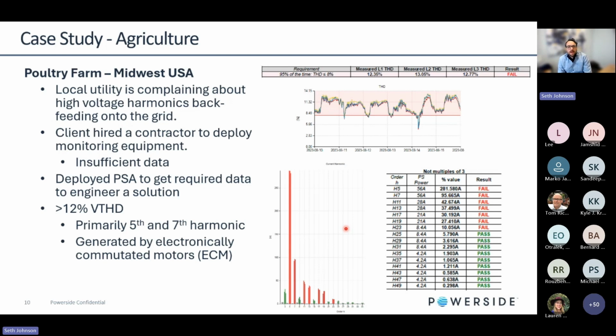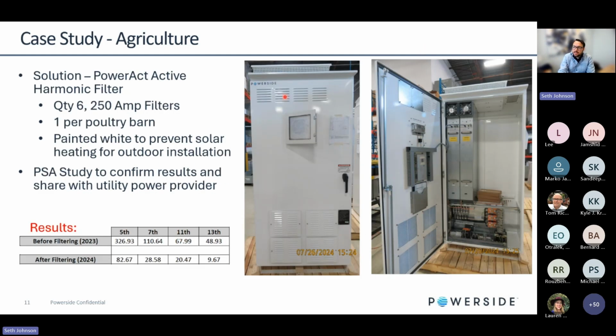And so what we offered was our Power Act product line. And you can see images here of the actual units that we shipped this client. We shipped a total of 6 of them for this client, 1 per poultry barn. And they're 250 amp active filters. Now, we went with the larger enclosure because we have the ability to add additional modules in the active filter if they expand the load or they need further correction.